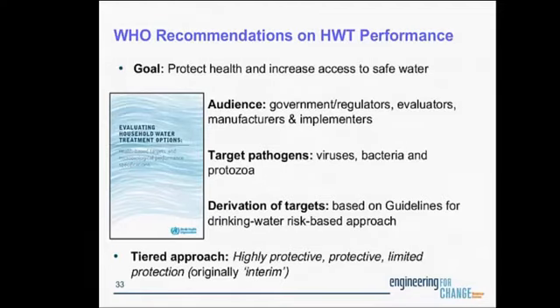The target organisms chosen in the evaluation of a product's performance through laboratory testing represent the classes of pathogens in water, and just like Danielle mentioned, that's bacteria, virus, and protozoa. And the organisms that were selected for the testing are valuable in that they are well documented as laboratory test organisms, may have varying degrees of susceptibility to commonly used drinking water disinfectants like Cryptosporidium, as Danielle mentioned, represent an array of particle sizes and surface properties, or are actual pathogens in and of themselves. Detailed information about the testing, including the specific test organisms, can be found on the scheme website, which I will share that link at the end of my slides.